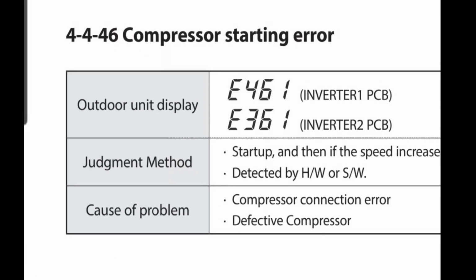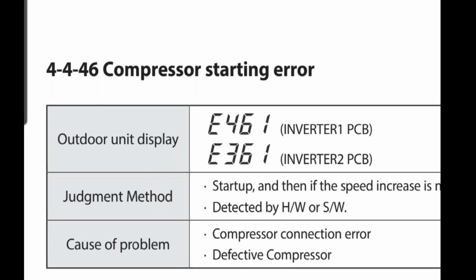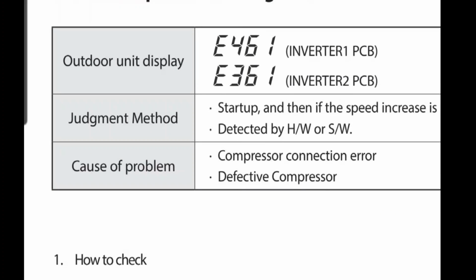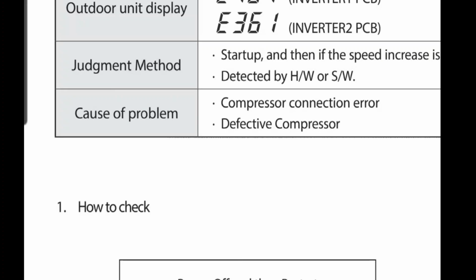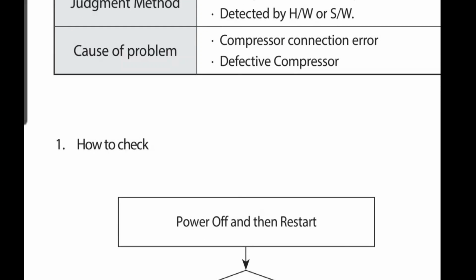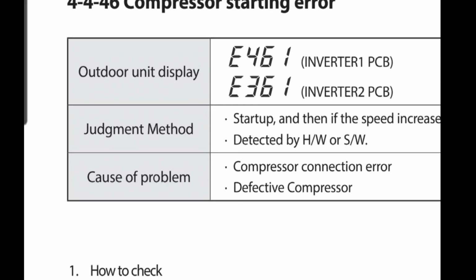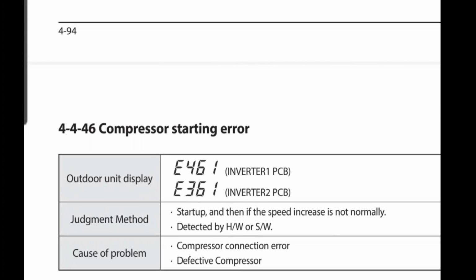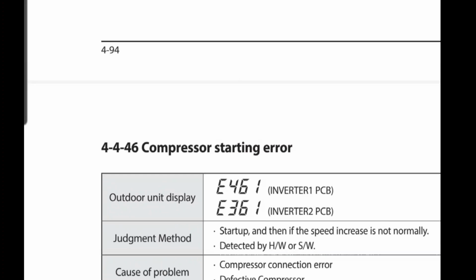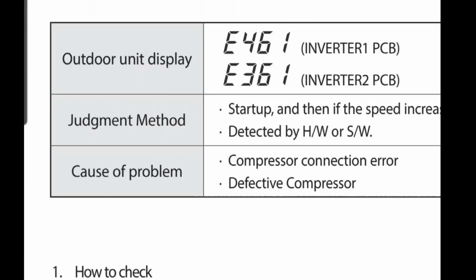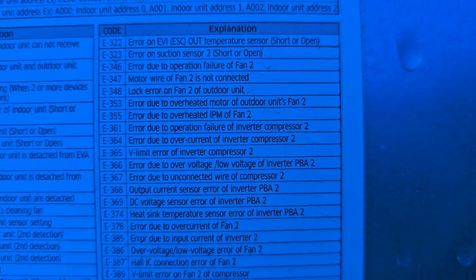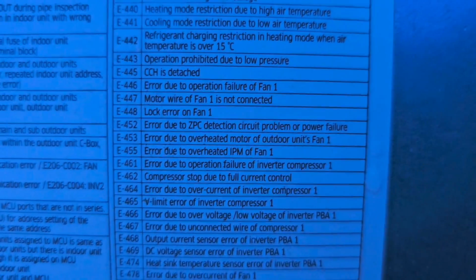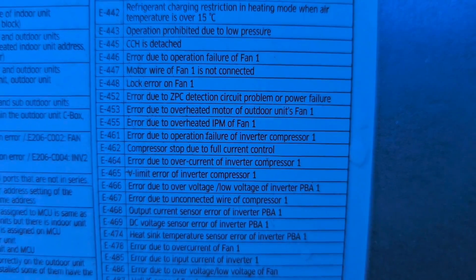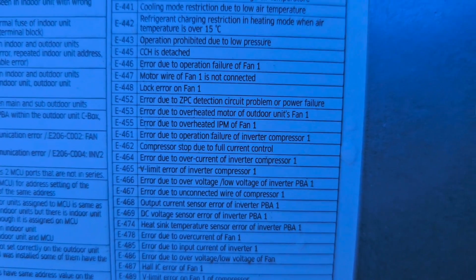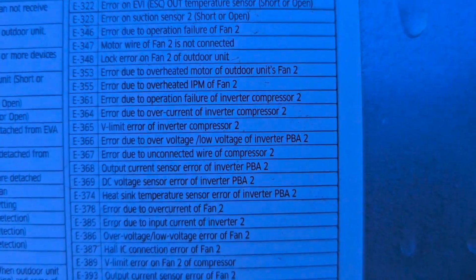So error code E461 has to do with inverter board 1 because there's 2 inverter boards. And then E361 is inverter board 2. There's 2 compressors, 2 inverter boards. And it says the cause could be a compressor connection error or a defective compressor. And it says the way you judge that is if upon startup the speed doesn't increase normally, then it could be your compressor. Here's error 361, error due to operation failure of inverter compressor 2. Then we go to E461, which is right here, error due to operation failure of inverter compressor 1. So E461 is for 1, E361 is for 2.